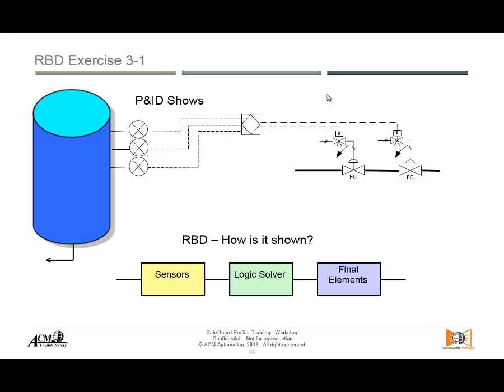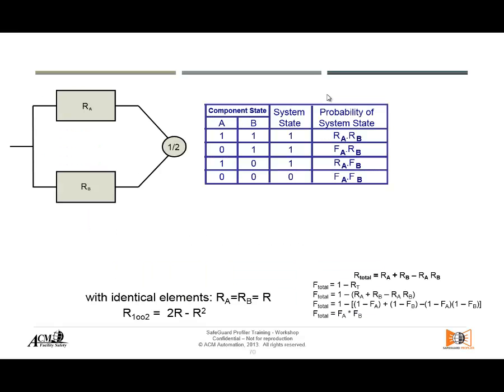For one out of two, this is the RBD representation. It is very important to have the two elements in parallel. The only way to know they are in a one-out-of-two configuration is because we put '1oo2' inside the circle. A two-out-of-two would simply be two boxes in series. This circle annotation becomes especially apparent when you go to a two-out-of-three configuration.